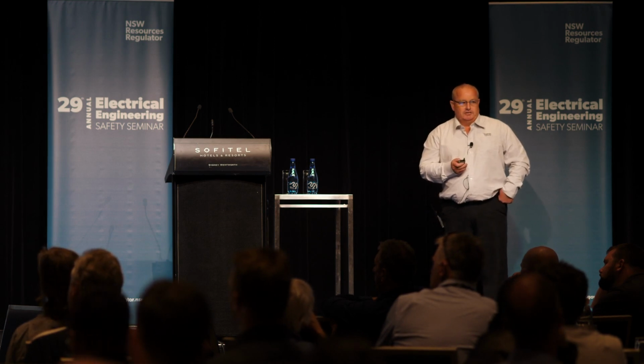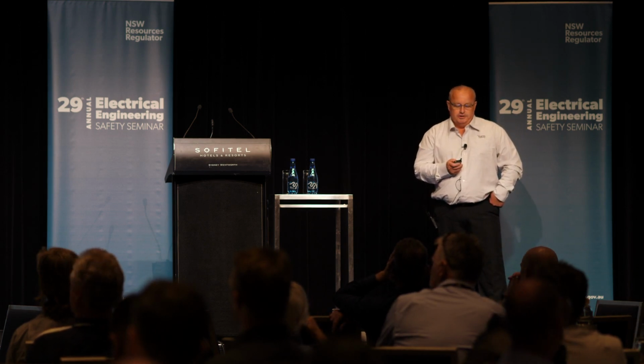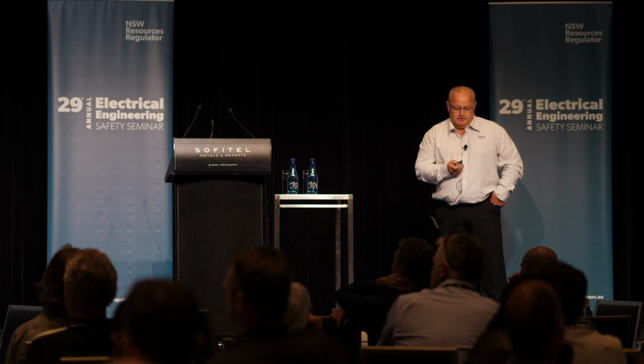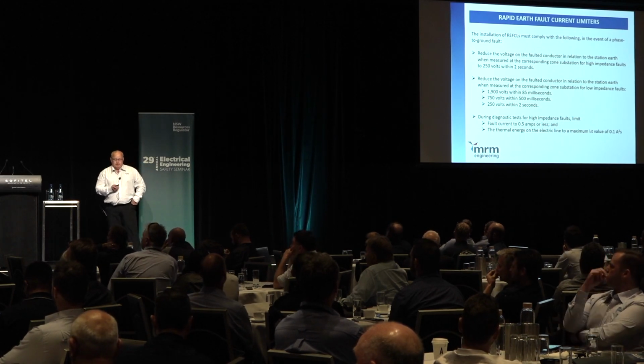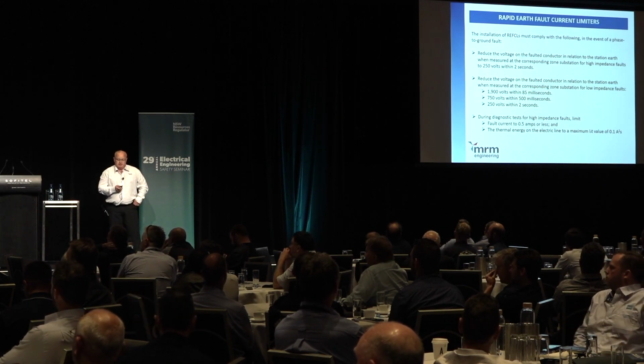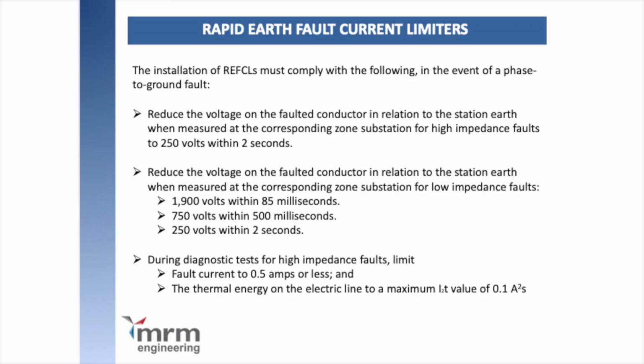So the new standards are specified for line works within the defined areas. They're picking on certain areas within the Victoria network where these faults occurred, in the hope that they can reduce the risks around these areas. So they ended up developing a standard with specifications for the rapid earth fault current limiters. It must reduce the voltage in a faulted conductor in relation to the station earth, when measured at the corresponding substation, for high impedance faults down to 250 volts within 2 seconds. Their standard system is just a TNS system with no fault limitation. So now they're aiming to get that voltage down to 250 volts.